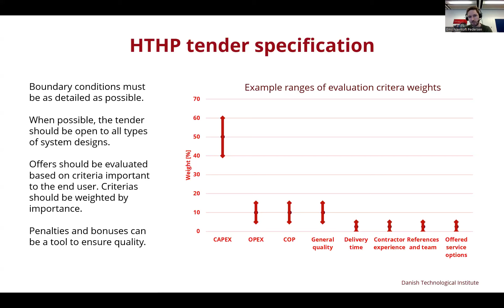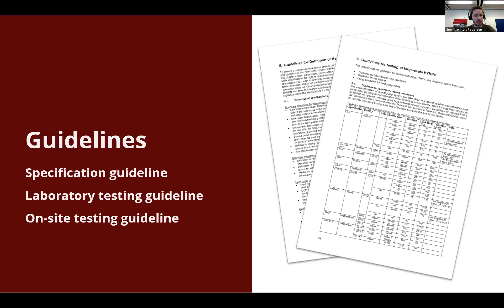The report also goes into three guidelines. The first is the specification guideline, which helps with specifying all the important things to remember in a heat pump project. The second guideline is a laboratory testing guideline on how a factory or laboratory test should be performed. Lastly, the on-site testing guideline is for how a site acceptance test is performed for a large industrial heat pump.